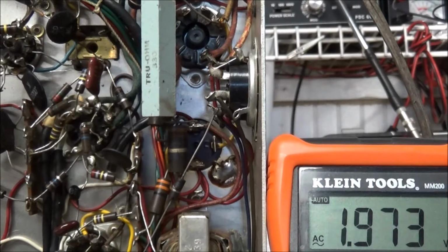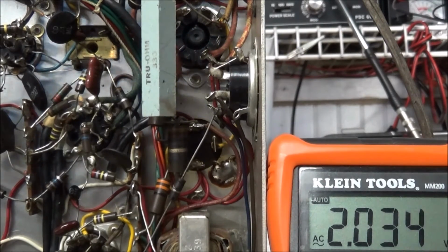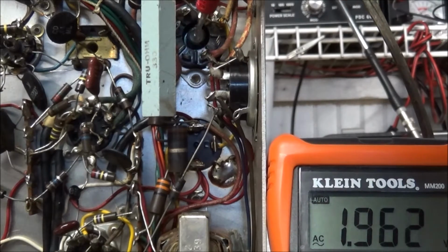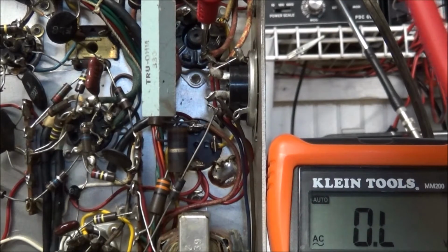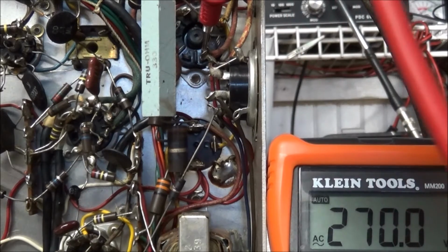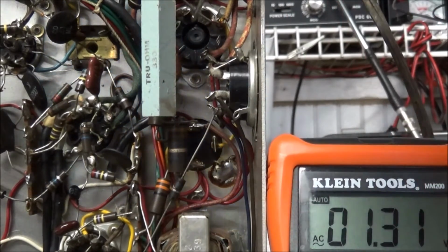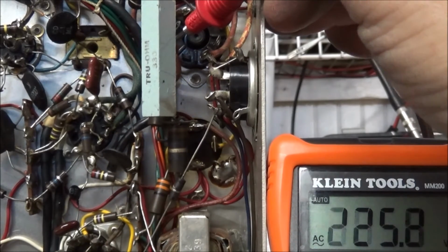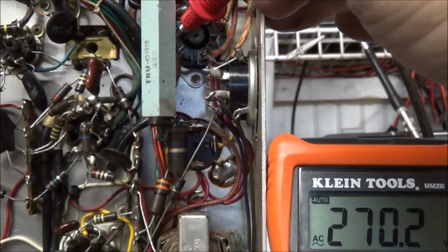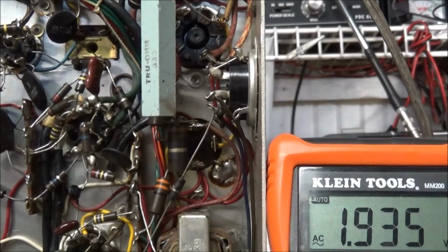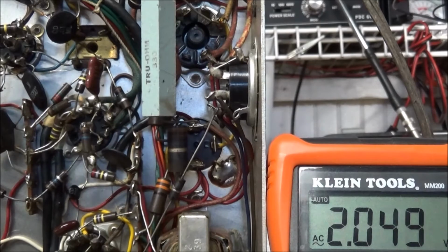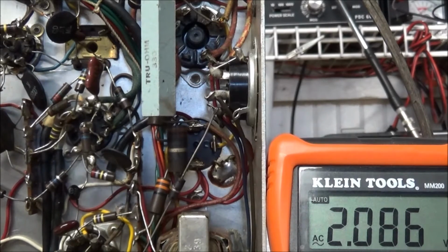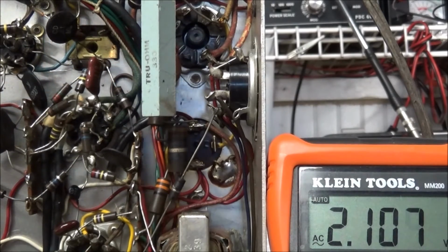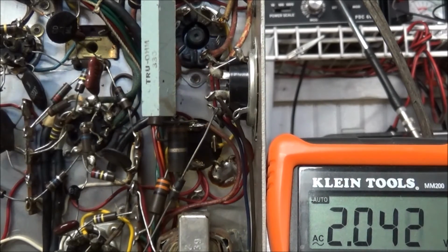I have the voltmeter grounded to the chassis, since the center tap of the transformer is grounded, so we're checking each leg of the AC side of the transformer. We have approximately 270 volts AC on each leg. It usually should be around 250 volts, so I'm thinking someone changed this to a different transformer with a higher output and used a dropping resistor.